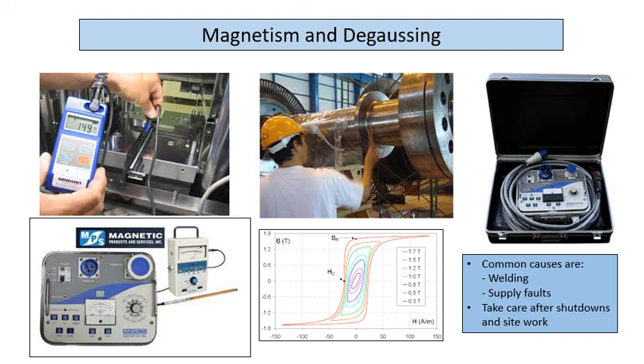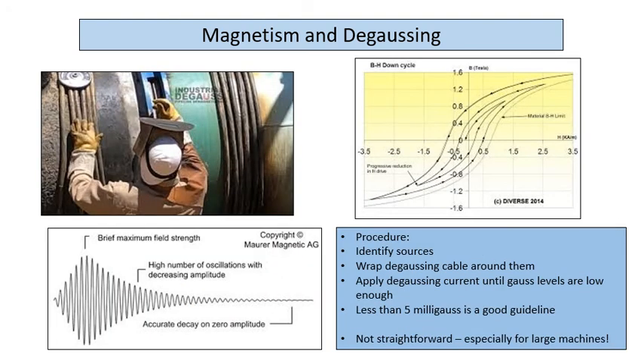So you have to put a substantial current through that coil, and then you reverse cycle it through the BH curve so that it continually cycles and goes to zero. You don't need to use a sinusoidal supply. These auto degauss units put a switched DC, so they go, let's say, 100 amps positive for like 2 seconds, then they switch 90 amps negative for 2 seconds, and they cycle down like that, and that demagnetizes the component.